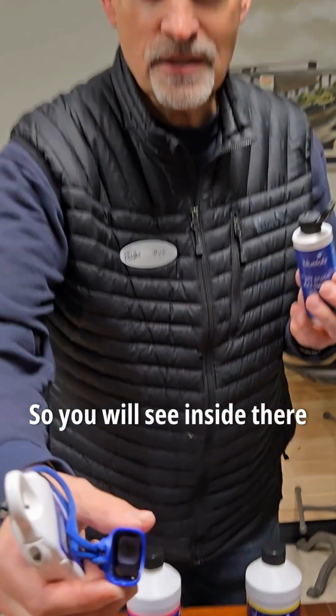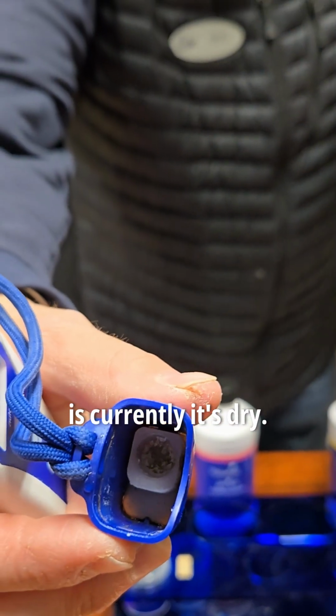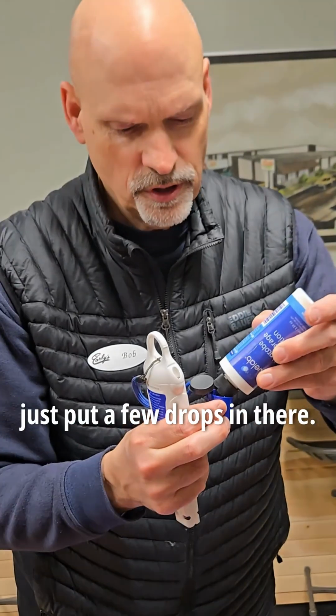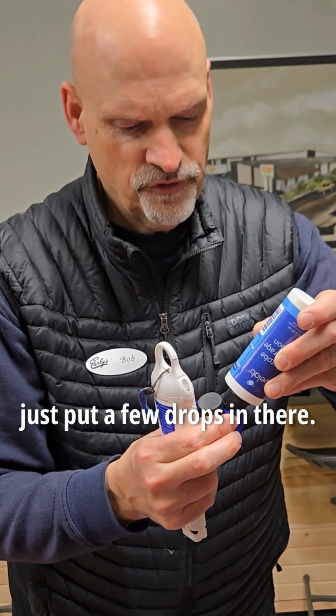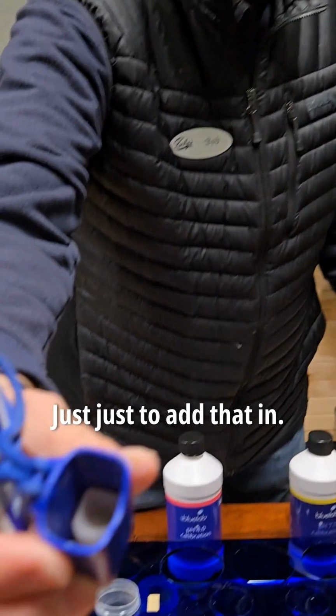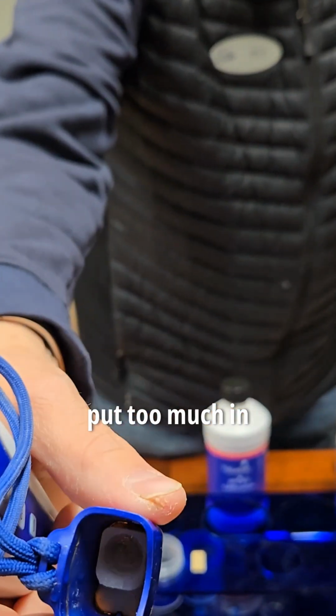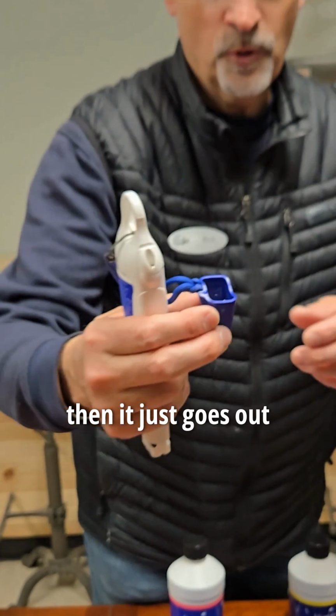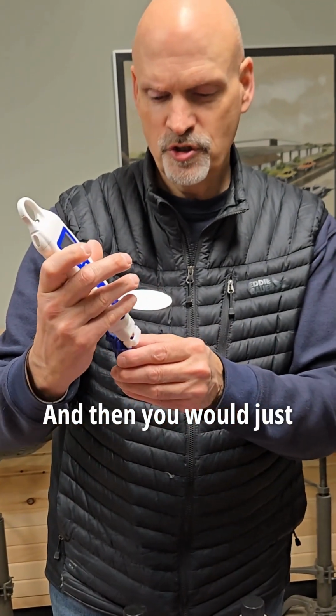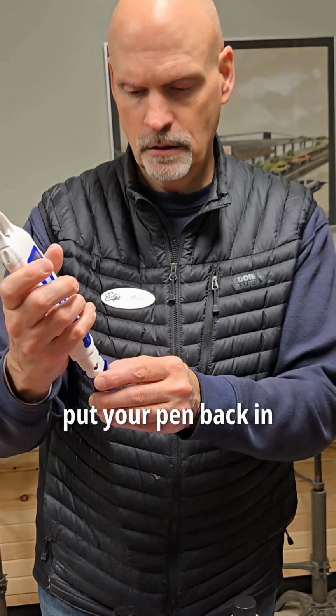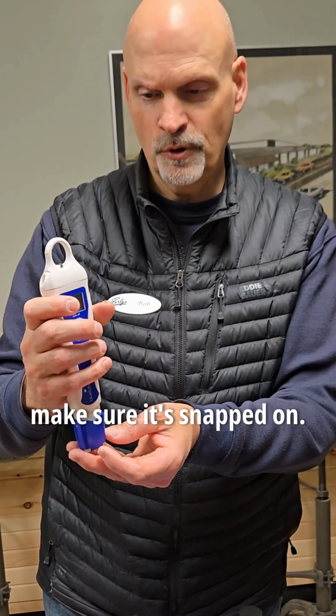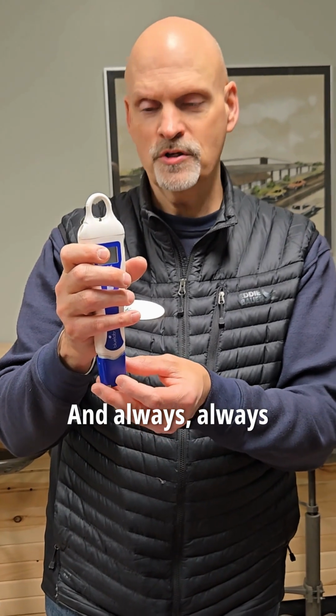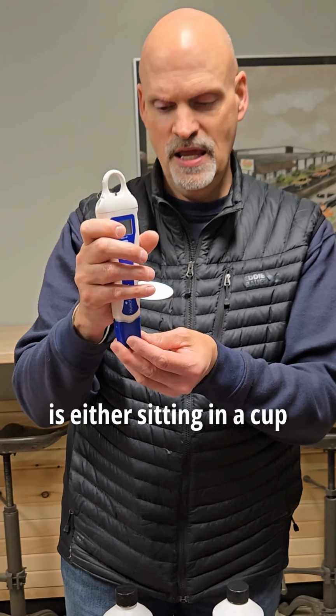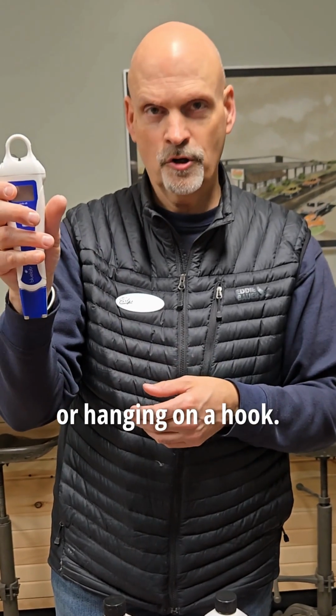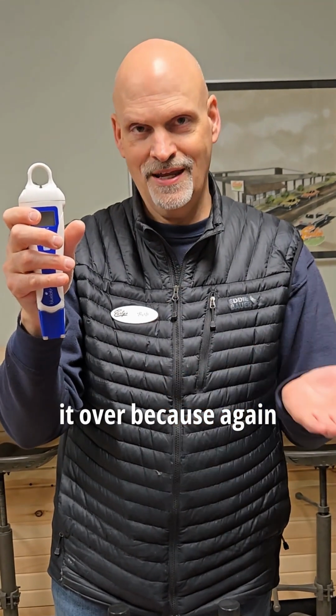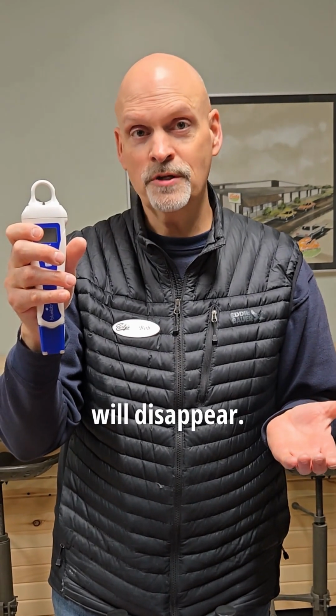So you will see inside there that this one is currently dry. So I am going to put a few drops in there just to add that in. You don't want to put too much in, because if you do, then it just goes out when you put your pen in. And then you would just put your pen back into the cap, make sure it's snapped on, and always make sure that your pen is either sitting in a cup or hanging on a hook. You never want to lay it over, because again, that KCl solution will disappear.